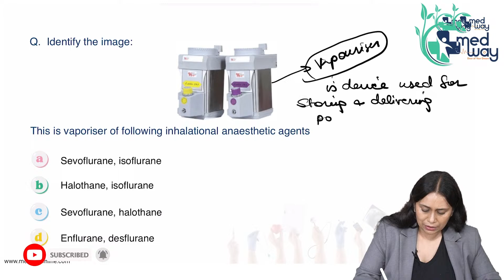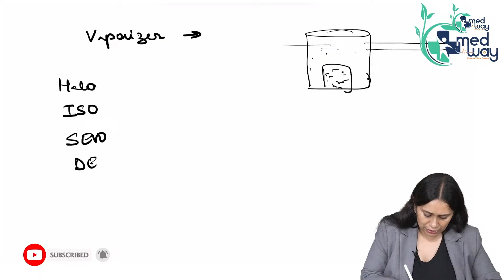This is a vaporizer of which agent? Now, vaporizers are color coded. Remember a few questions we need to know about the vaporizer. It is used for storing the inhalational agent in liquid form. The vaporizer vaporizes it, adds it to the carrier gas, and together they come out of the bypass channel of the vaporizer. A specific vaporizer is used for every agent. So, we have the inhalational agents halothane, isoflurane, sevoflurane, and desflurane.